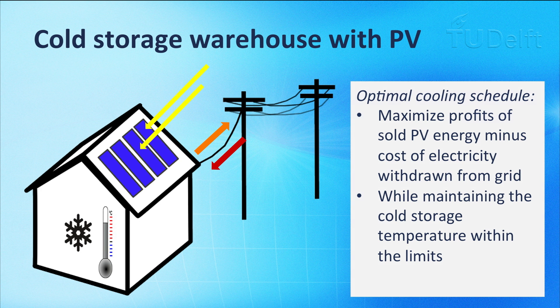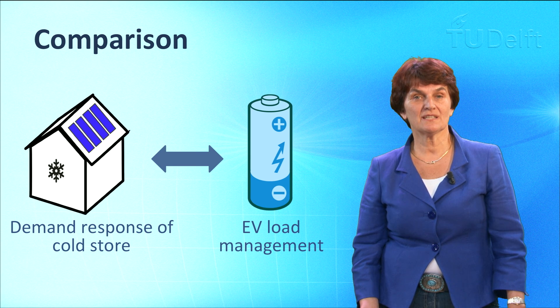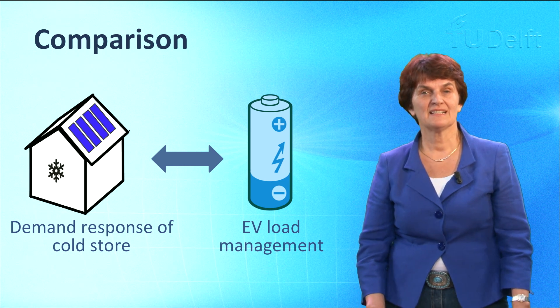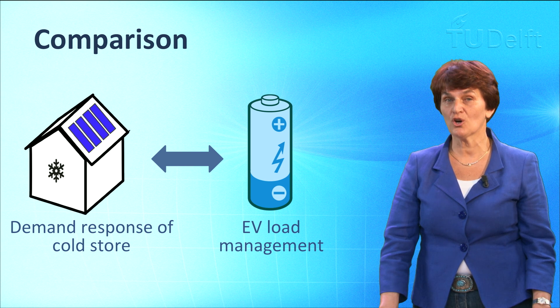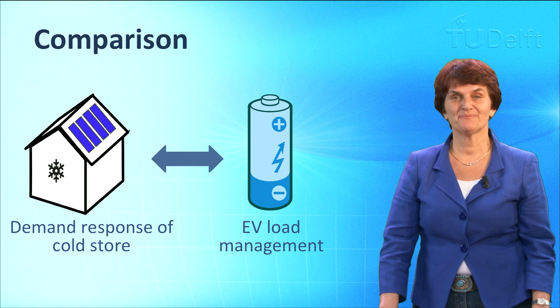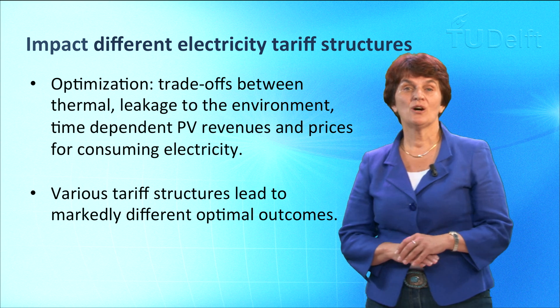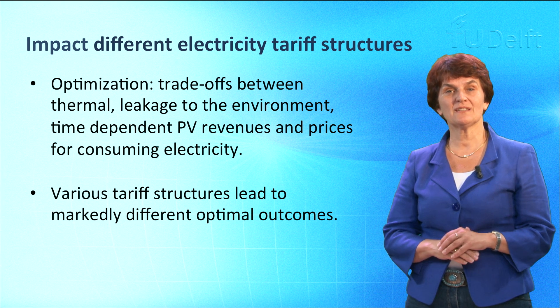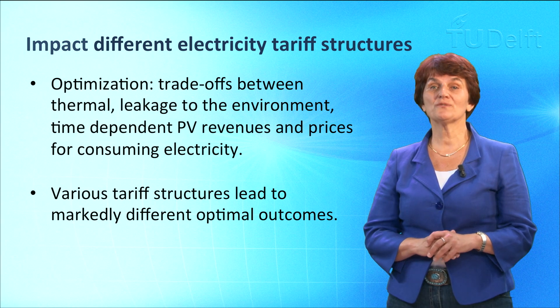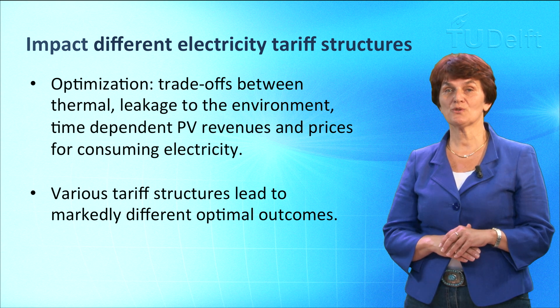There is a clear similarity between EV load management and demand response of a cold store. An approximation of temperature dynamics of the cold store is similar to the description of energy content of an EV battery in a car. Instead of electrochemical energy stored in a battery, we have here heat stored in the cold store warehouse. It is interesting to investigate the influence of different electricity tariff structures on the optimal cooling schedule and to optimize this. The cooling trajectories can be understood in terms of trade-offs — in this case, trade-offs between thermal leakage to the environment, time-dependent PV revenues, and prices for consuming electricity.